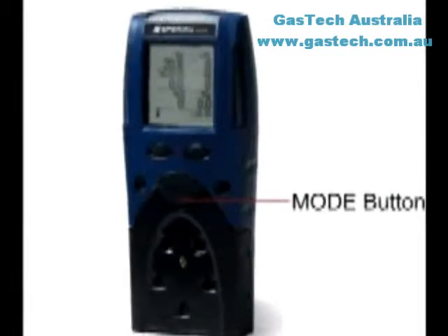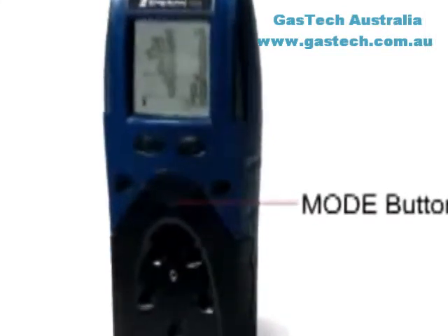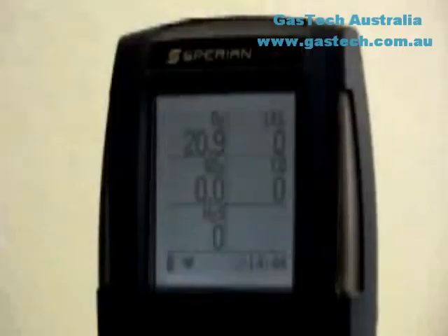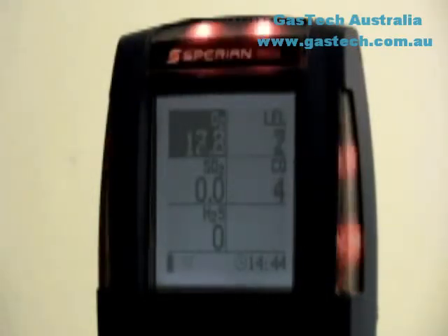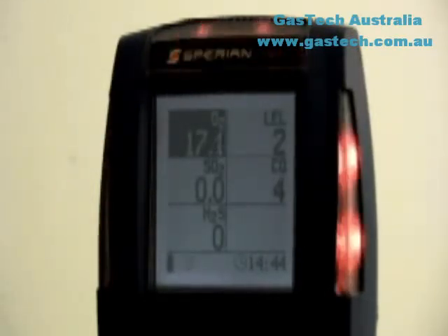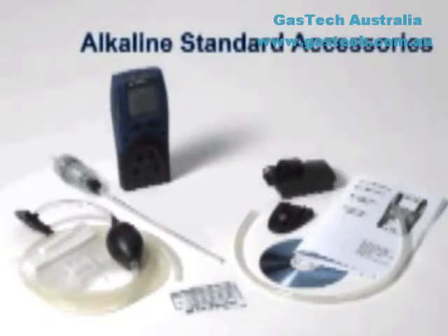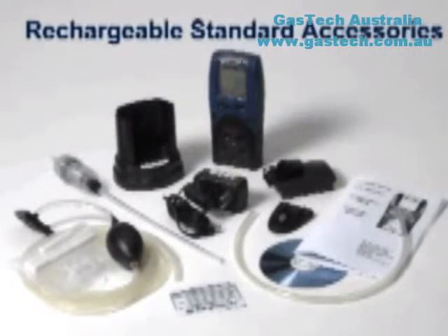Upon successful calibration of a sensor, the PHD6 will beep, show the adjusted reading for the calibrated sensor, and then move on to the next sensor. The PHD6 will briefly show the maximum adjustment values screen. The maximum adjustment values for the LEL and toxic sensors give an indication of the relative health of the sensors. As a sensor loses sensitivity, the maximum possible adjustment will decrease to approach the expected concentration of the calibration gas.